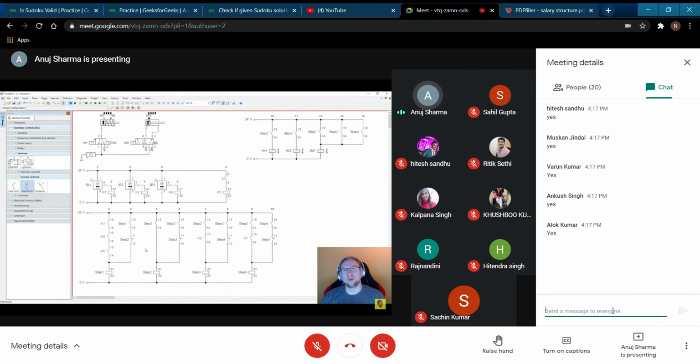And this something I want to be a time delay. I want this to be a time delay, and we have so-called relays with a switch on delay. This nice little guy here. There's also switch off delay, but let's only look at the switch on delay here. This one behaves the same way as those. It has contacts that we can activate, deactivate, open, close, but with a time delay. So it will activate 1, 2, 3, 4, 5, and then the contact will close, not immediately. So if I put that in here, in parallel to my step 1, somehow.